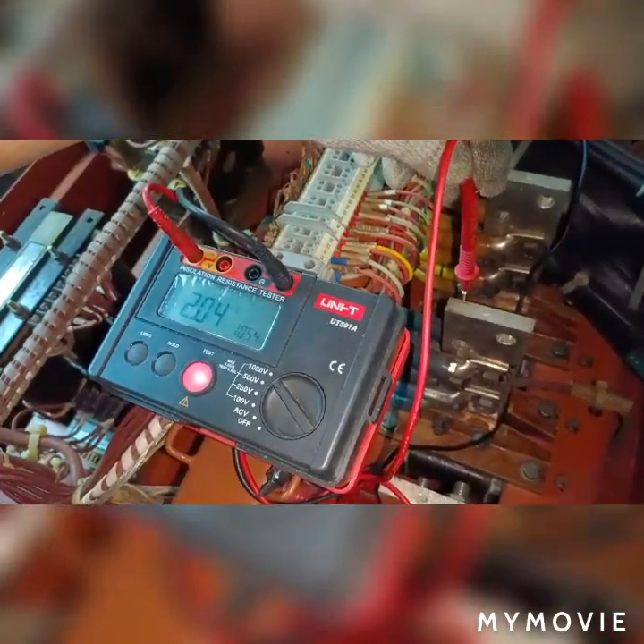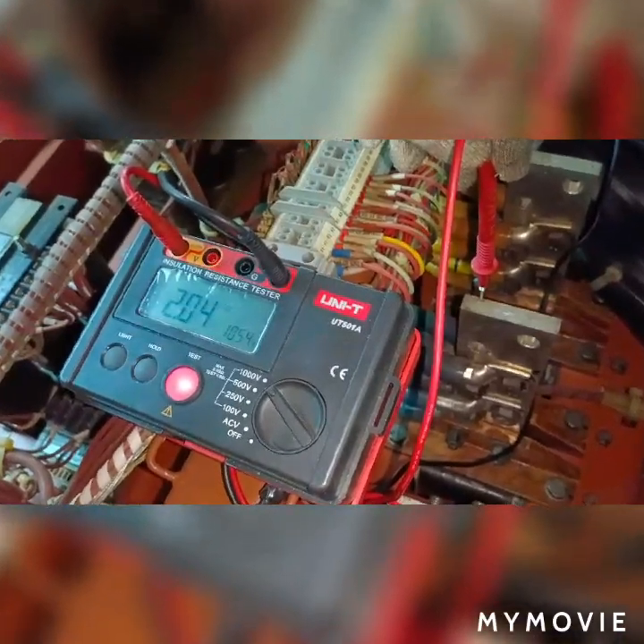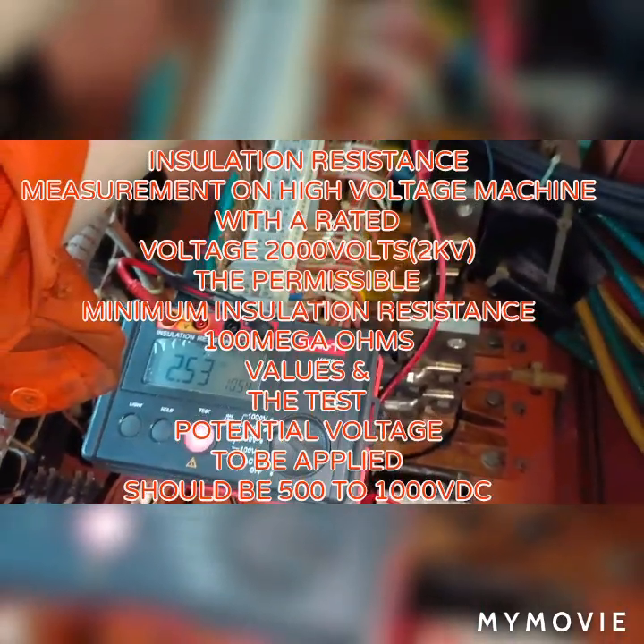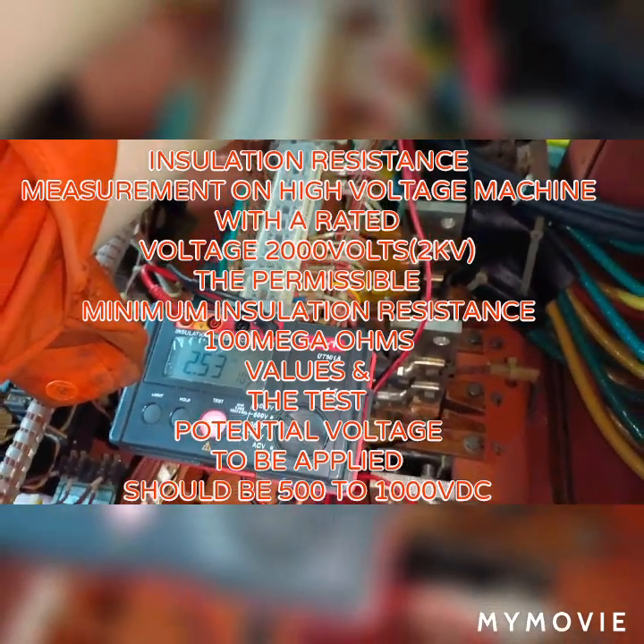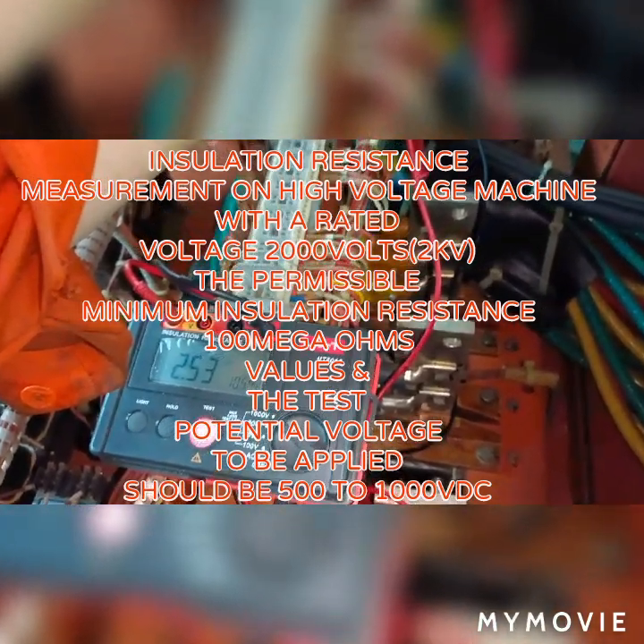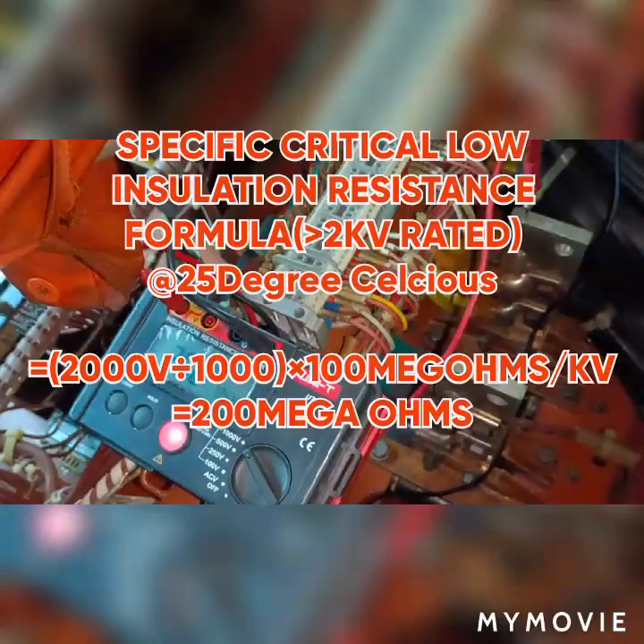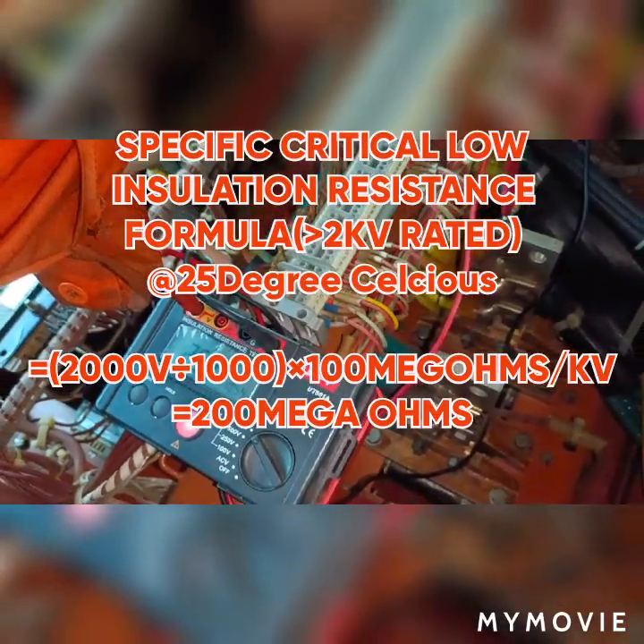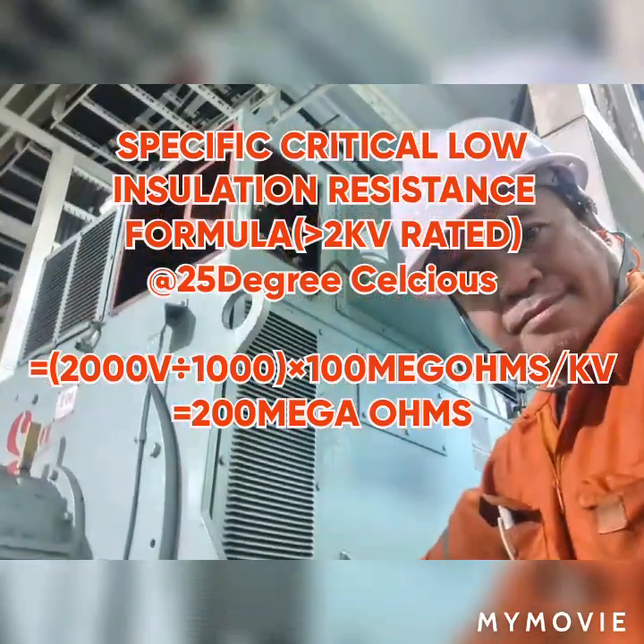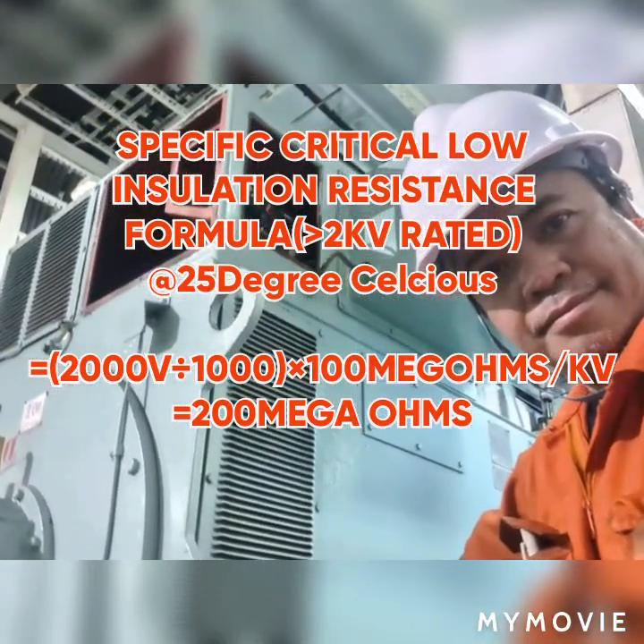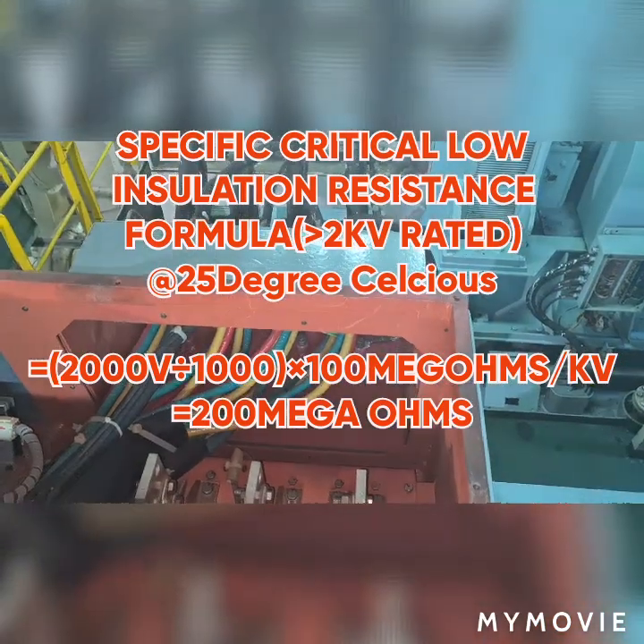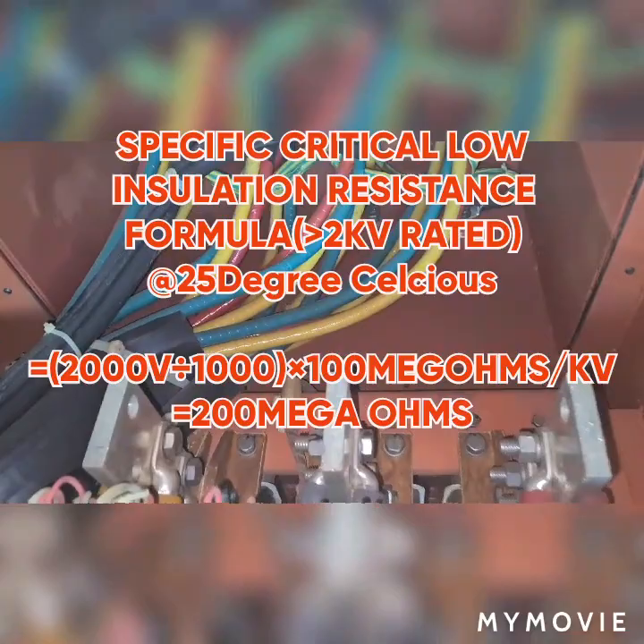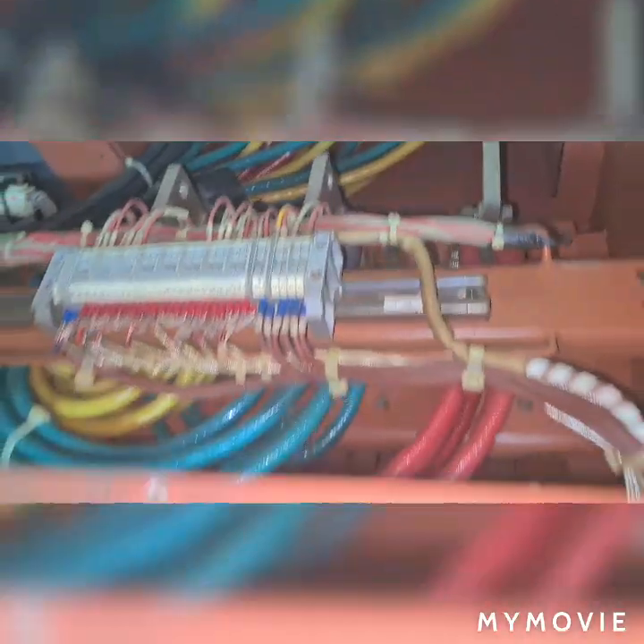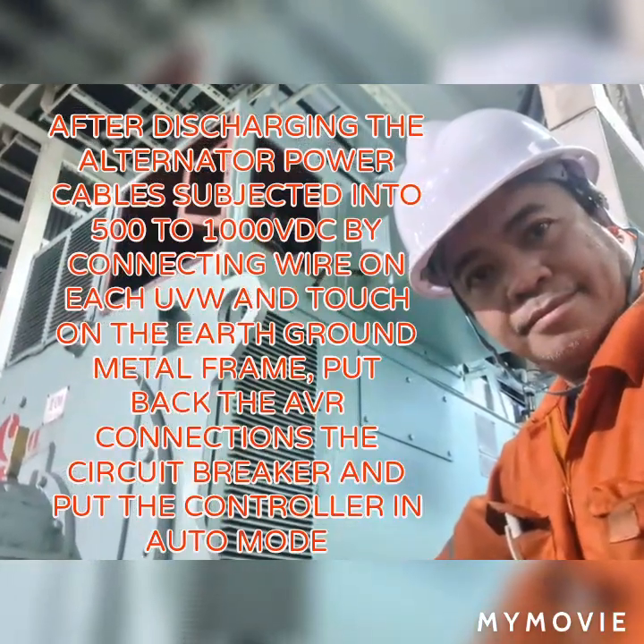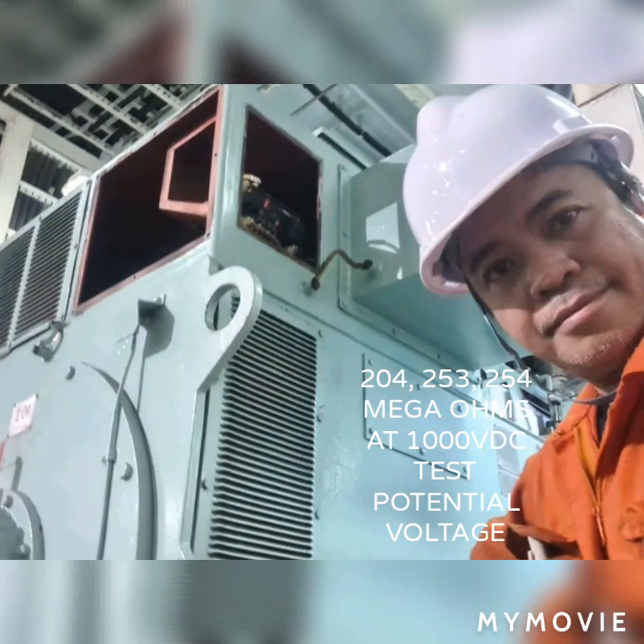You must also take note of high voltage rated machines more than 2 kilovolts. After a long period of operation, the critical insulation value is 100 megaohms per kilovolt, or you may compute 2000 volts divided by 1000 and multiplied by 100, and you may get about 200 megaohms. You must consider this as a rule of thumb when doing a Megger insulation check for alternators and power generators.